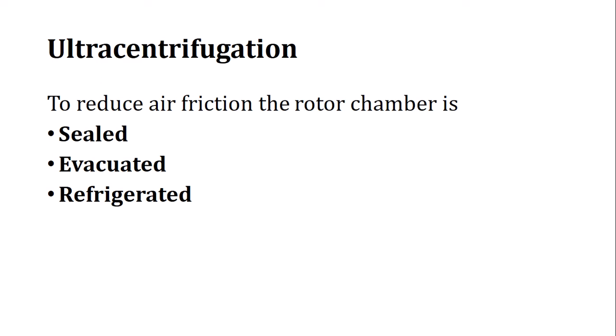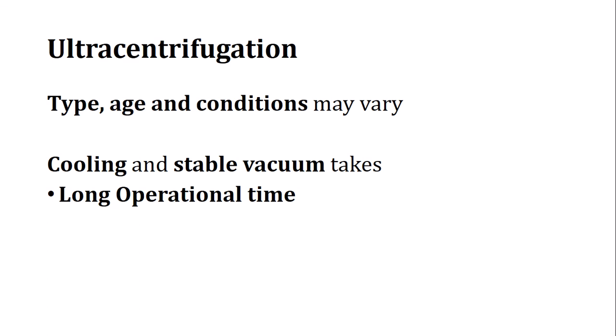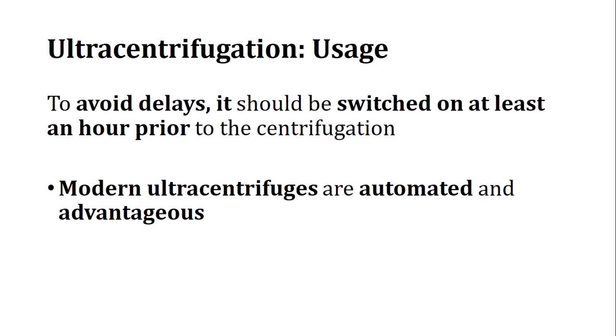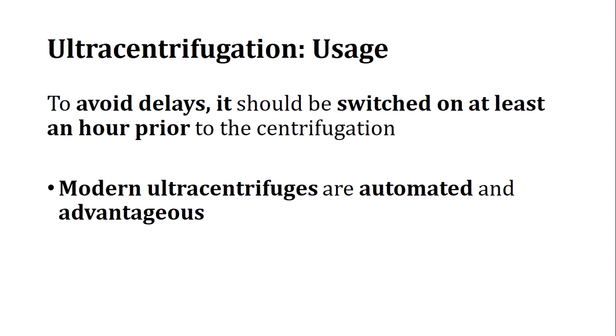Depending on the type, age, and condition of the centrifuge, achieving a stable vacuum and proper cooling can take a large amount of operational time. For older models especially, we switch it on at least one hour prior to the centrifugation process. Modern ultracentrifuges are automated and take less time to reach operational conditions.